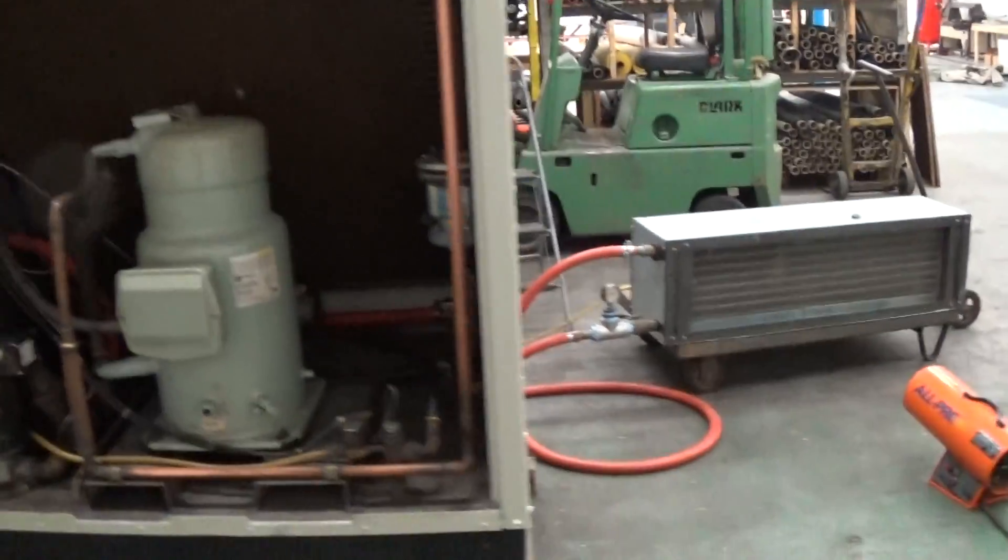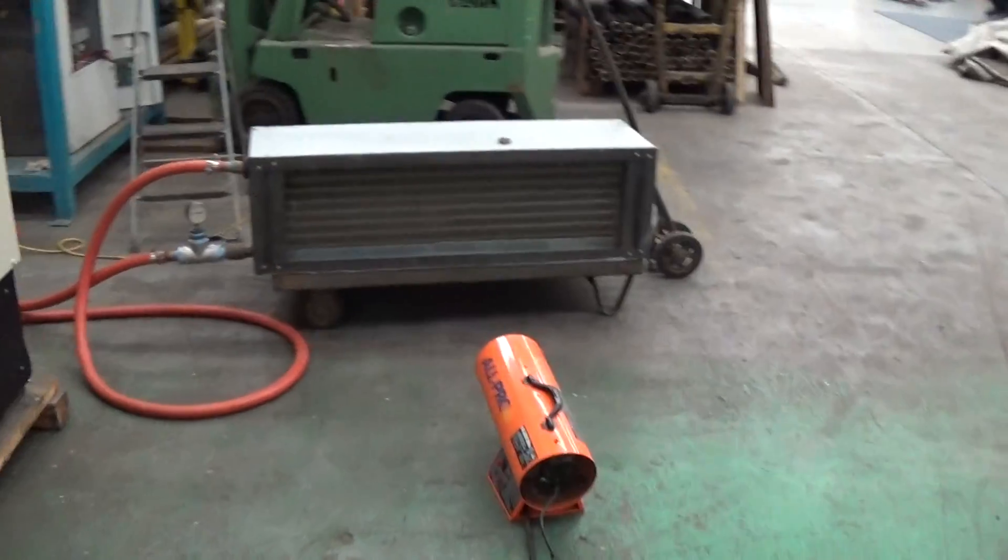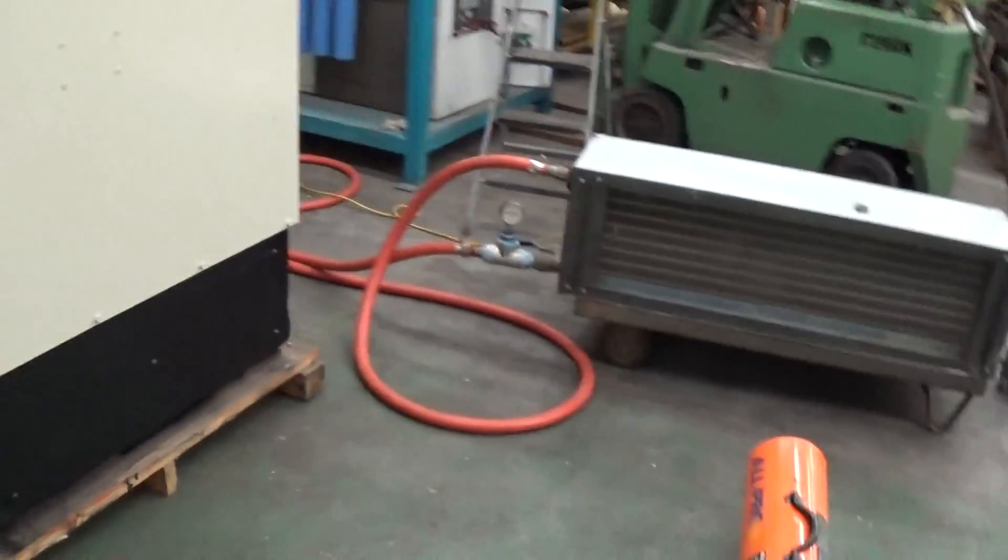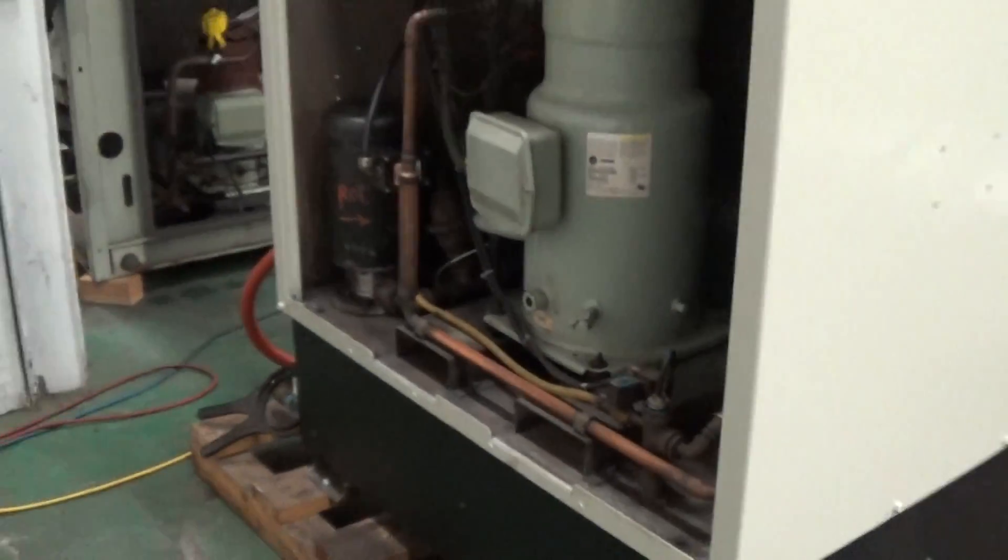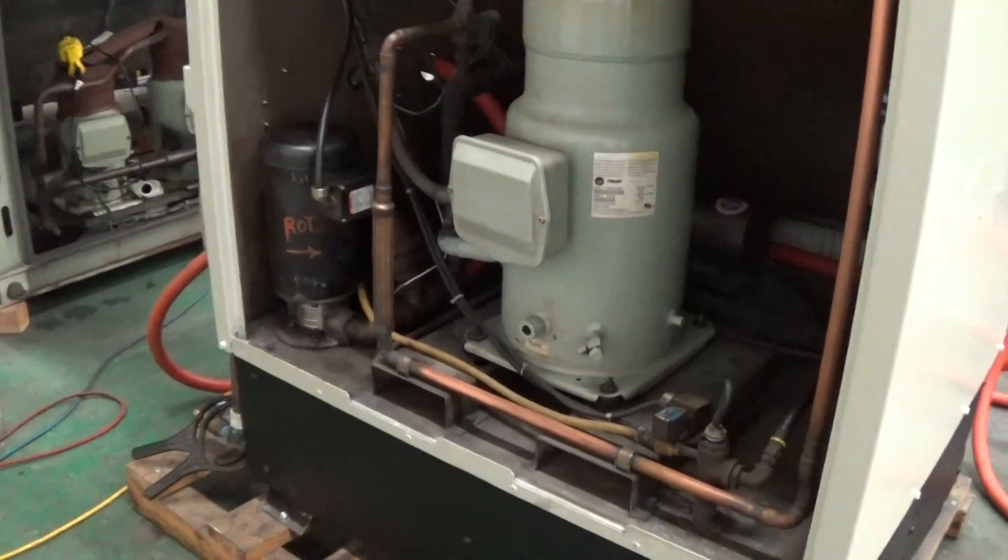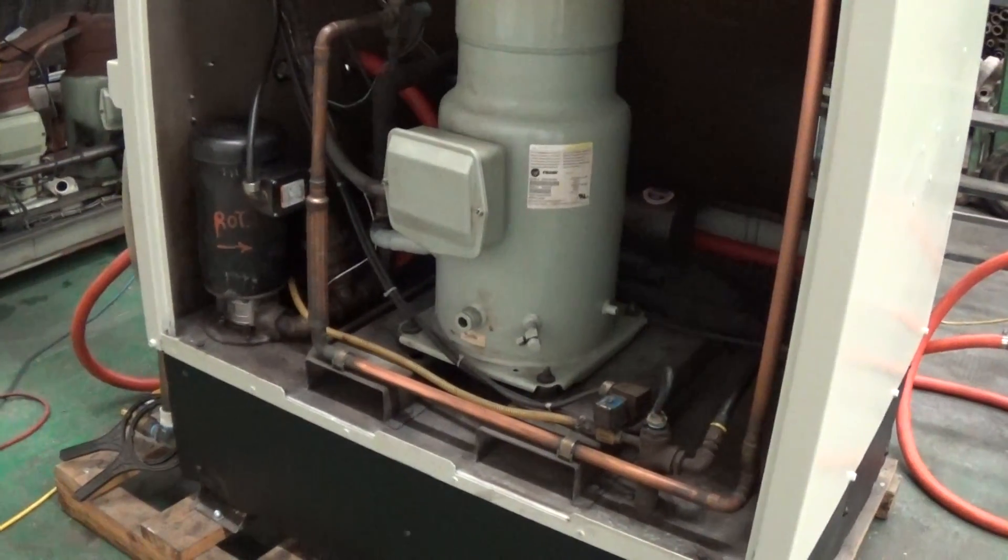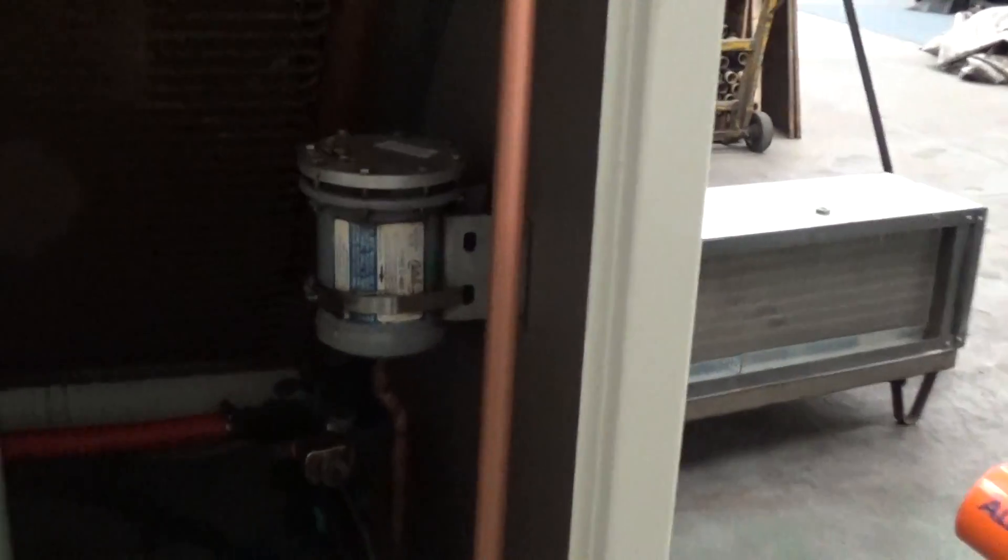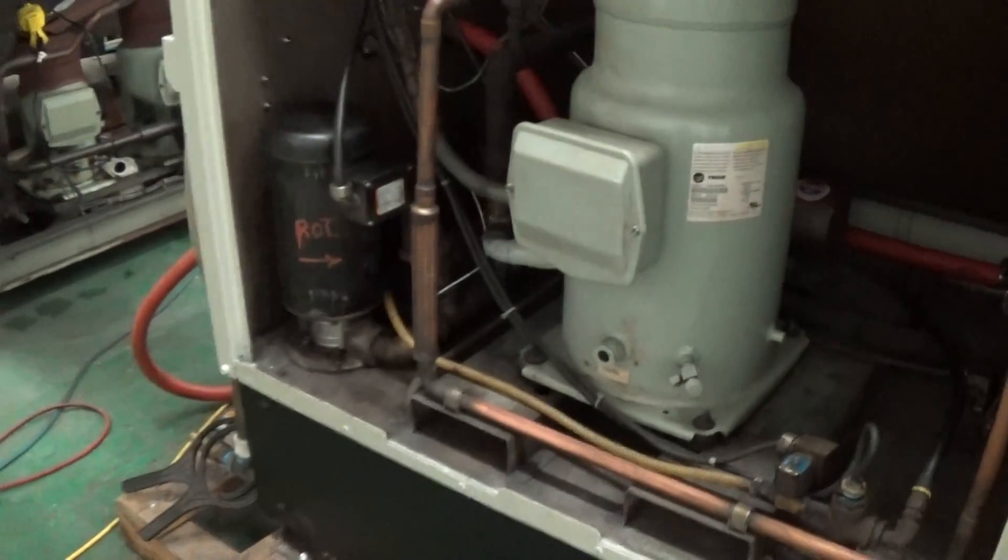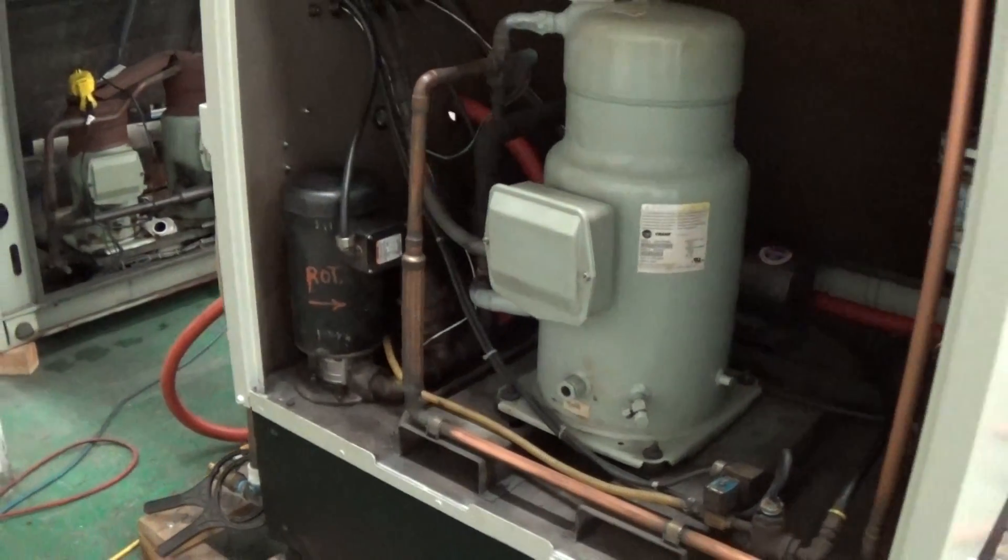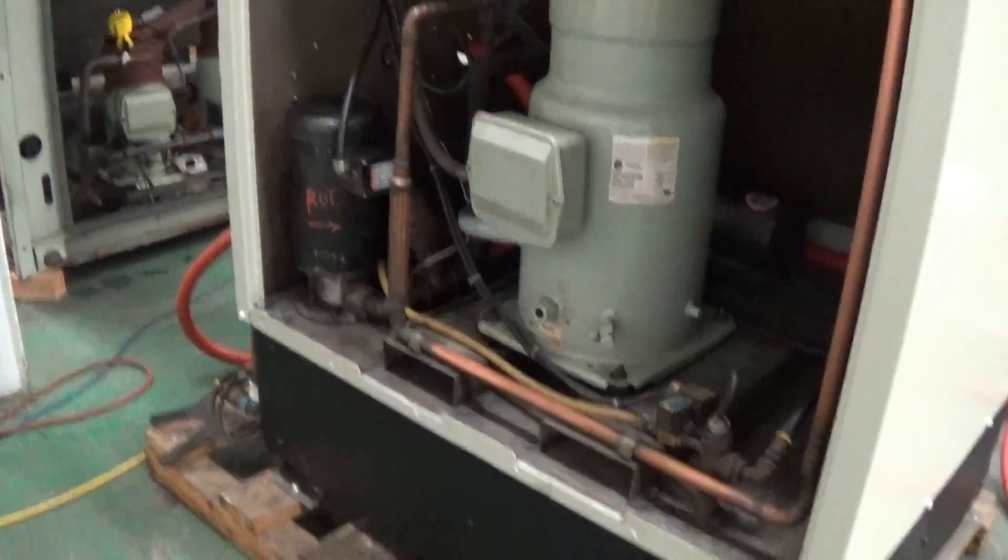So this unit has been running great. As I mentioned, in addition to the cleaning, repainting and stuff, we did put in a fresh virgin charge, a new dryer. In fact, we went ahead and labeled the date and the new dryer went in. And some new bearings on the pump.